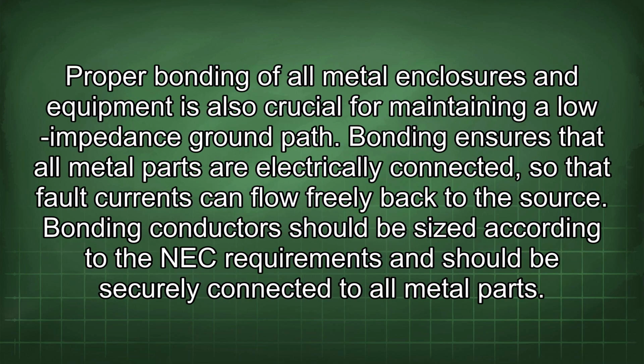Proper bonding of all metal enclosures and equipment is also crucial for maintaining a low impedance ground path. Bonding ensures that all metal parts are electrically connected, so that fault currents can flow freely back to the source. Bonding conductors should be sized according to the NEC requirements and should be securely connected to all metal parts.